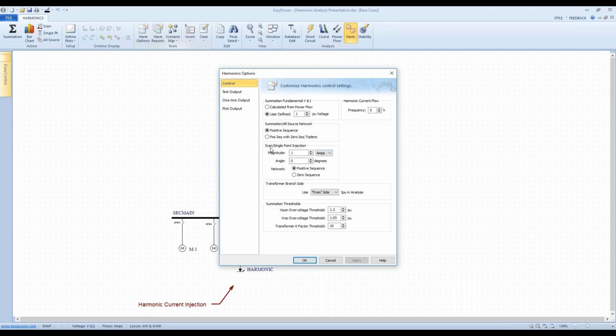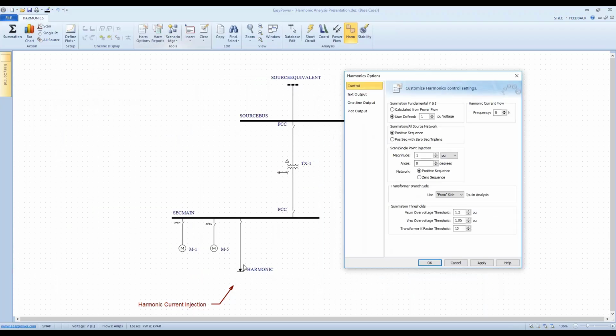Okay, and this is for impedance scans. This is an impedance scan section, and you're saying, well, what is my current injection for an impedance scan? And if you use amps, then you're going to be injecting 1 amp into your model. You can have per unit here. In this case, it would be 1 per unit. So if you're injecting 1 per unit current here, you'd be injecting 418 amps. Okay, that would be a lot of harmonic current. If you're injecting amps to develop that impedance scan from this location, you would be injecting just 1 amp. So the impedance scan is developed based upon whether it's based on amps or based on per unit.